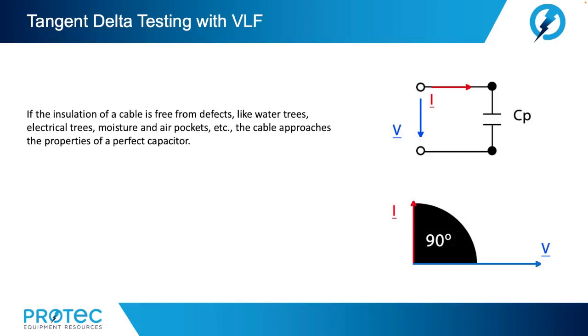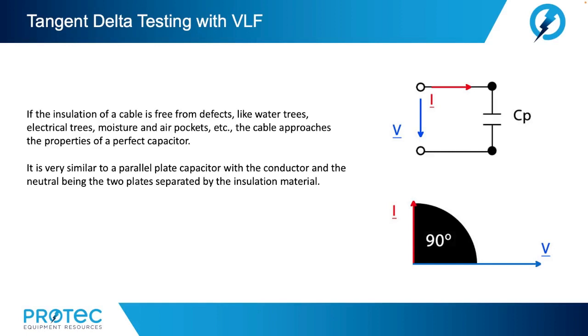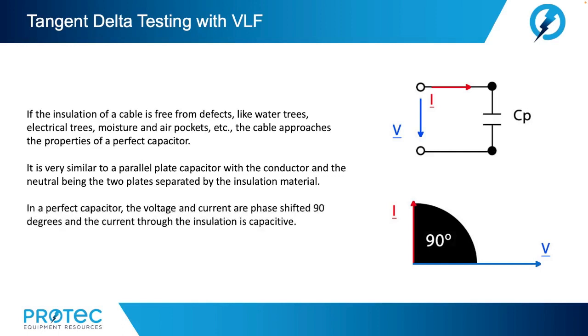Now, if the insulation of a cable is free from defects, like water trees, electrical trees, moisture, and air pockets, etc., the cable approaches the properties of a perfect capacitor. It is very similar to a parallel plate capacitor, with the conductor and the neutral being the two plates separated by the insulation material. In a perfect capacitor, the voltage and current are phase shifted 90 degrees, and the current through the insulation is capacitive current.